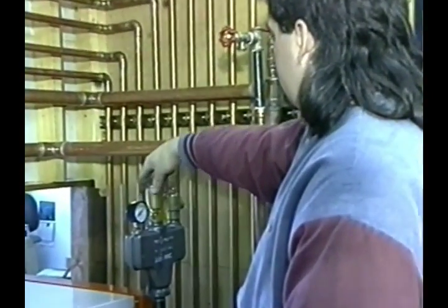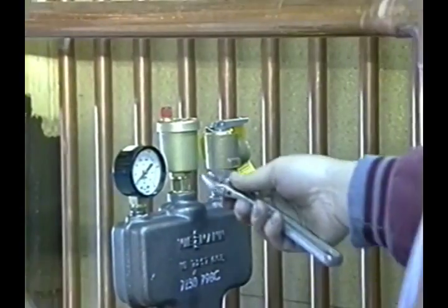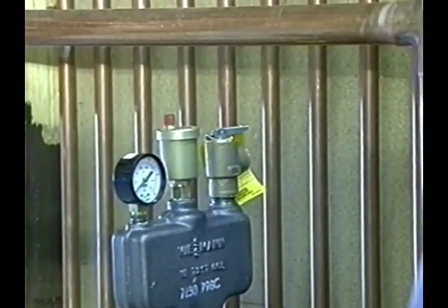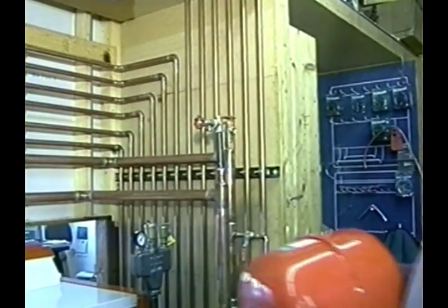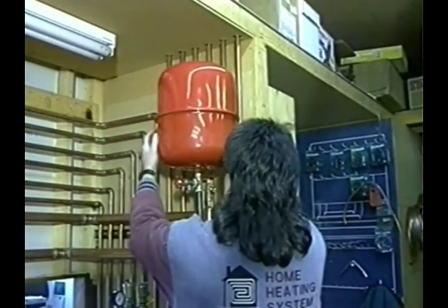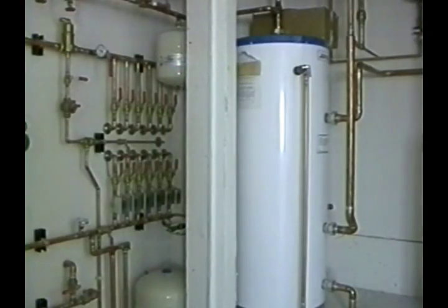The next thing is to install an air eliminator. This is typically placed on the supply side of the boiler system. An expansion tank comes next and is sometimes attached to the air eliminator. If an indirect water heater is being used, branch off from the supply side of the boiler piping to the supply inlet of the water heater. From the water heater return inlet, go back to the boiler return piping. A zone valve is placed on the supply side piping of the water heater and wired into the aquastat on the tank.